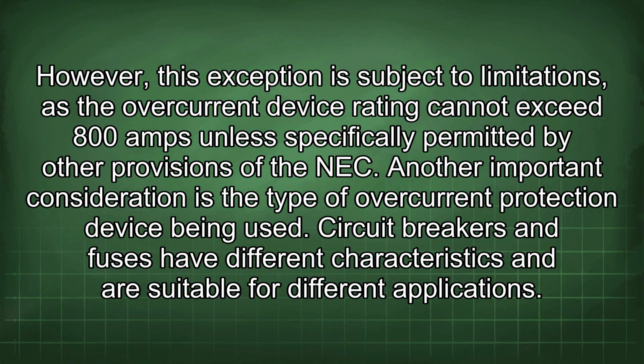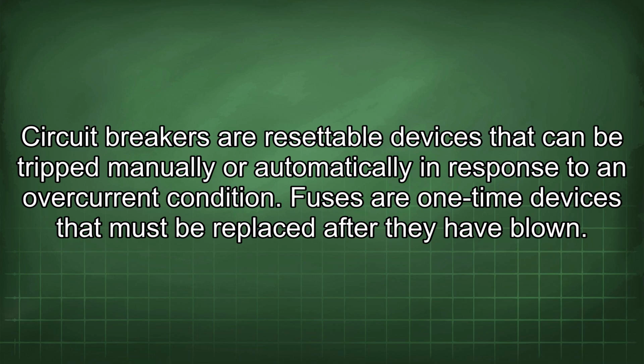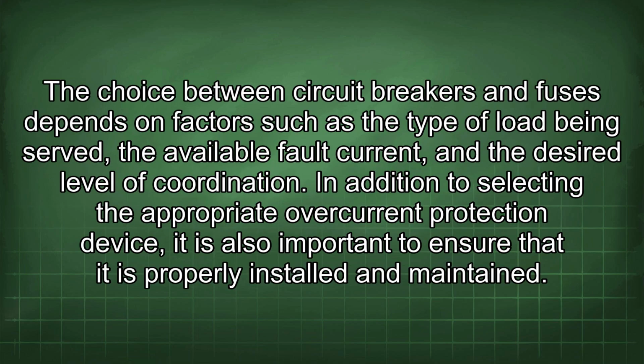Another important consideration is the type of overcurrent protection device being used. Circuit breakers and fuses have different characteristics and are suitable for different applications. Circuit breakers are resettable devices that can be tripped manually or automatically in response to an overcurrent condition. Fuses are one-time devices that must be replaced after they have blown. The choice between circuit breakers and fuses depends on factors such as the type of load being served, the available fault current, and the desired level of coordination.